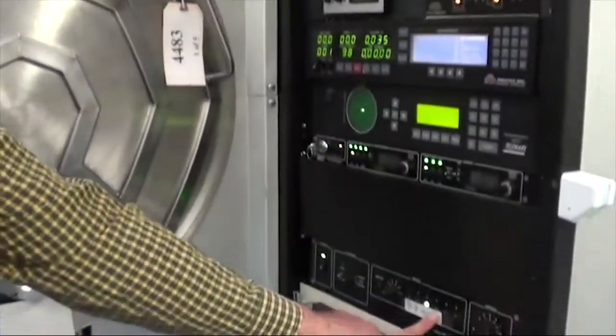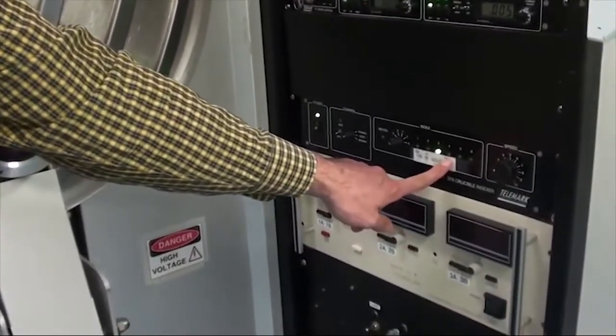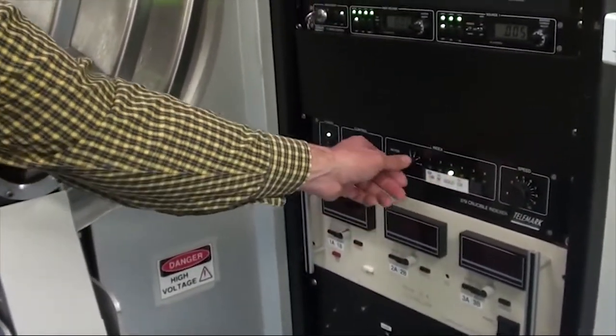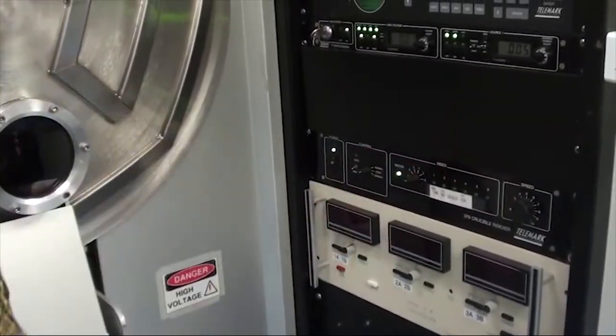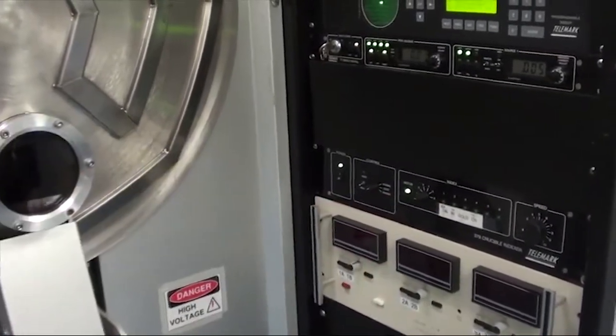There are some issues we found with this tool. One, you can tell the cryo does make a lot of noise. Next, the Crucible 4 select does not operate correctly. 1, 2, and 3 operate just fine. See that the motor comes on.